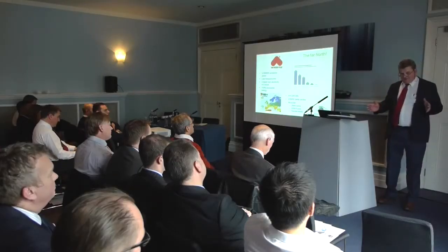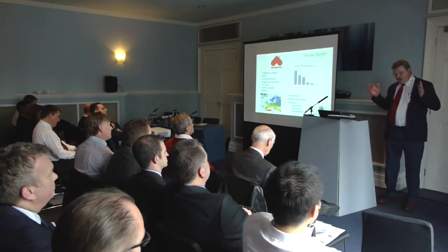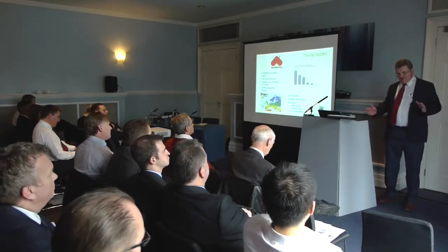However, there are only three small towns around the top end of that, so it isn't actually easy to get that 3,500 megawatts anywhere else. So they use it for data centres. I'm in a project now with a company called Hydro 66, building a 20 megawatt data centre, very modular, in 2 megawatt buildings, all off a central spine, but broken down into 200 kilowatt pods. Each rack averages about 10 to 15 kilowatts. So who's interested in this type?